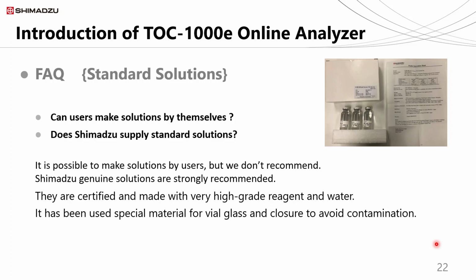Frequently asked questions, standard solutions. Can users make solutions by themselves? It is possible, but at Shimadzu, we never recommend it. Shimadzu genuine solutions are strongly recommended to avoid any mistakes while preparing. They are certified and made with very high-grade reagent and water. Special material for vial glass and closure to avoid contamination has also been used. It's very hard to prepare these high-level solutions at site. Solution quality directly affects the accuracy of the instrument. These solutions can be used for other Shimadzu TOC models as well, if needed.